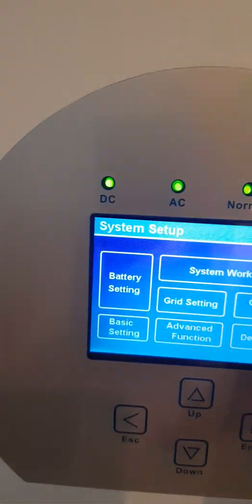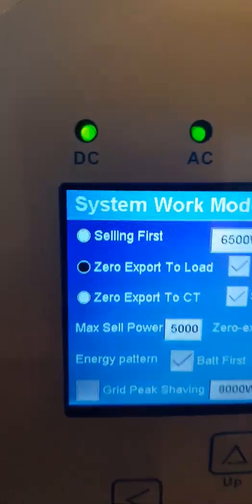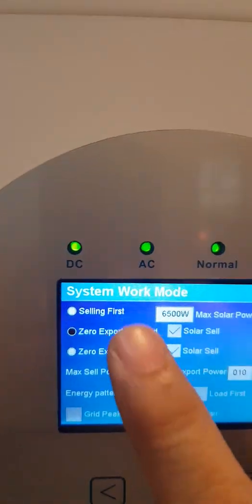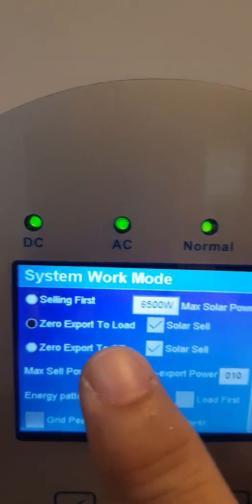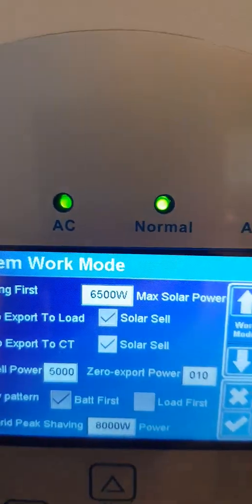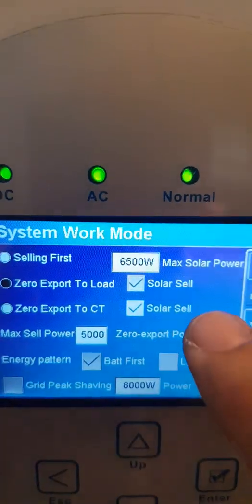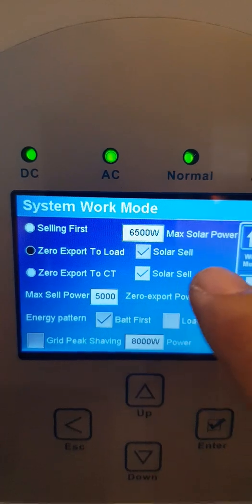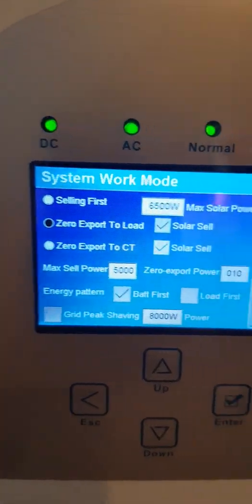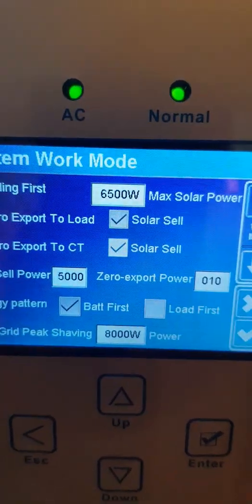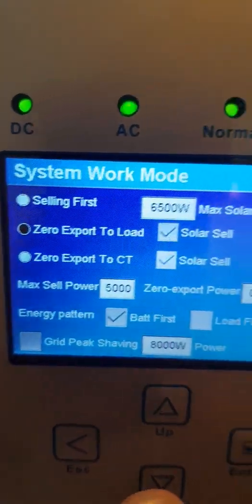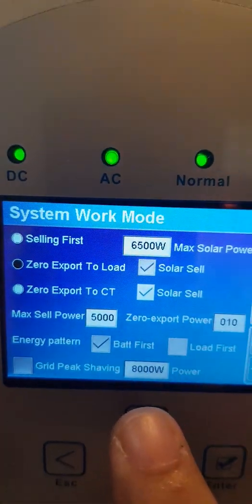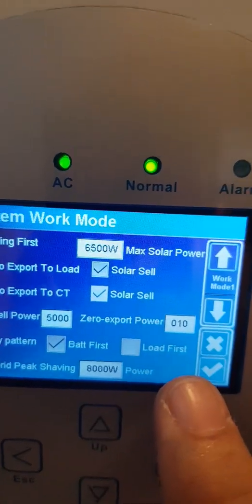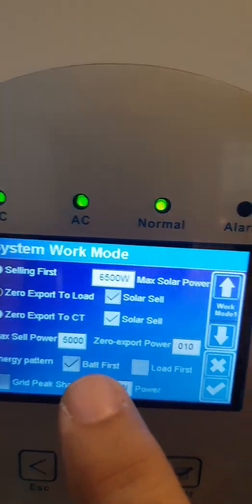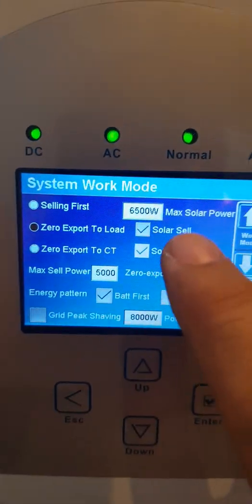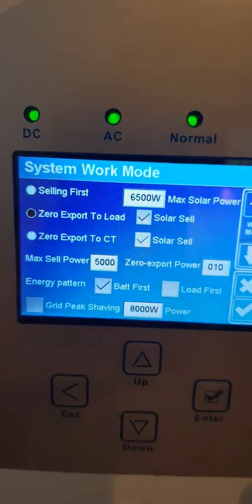Escape. So system work mode. If you're selling to grid, you can do selling first. Or right now we are using zero export to load. So solar sell is checked, so I can sell energy back to grid. You can turn this off so that the limiter will work and you will not export energy to the grid. So what else? So energy pattern, it means battery first, that you will charge the battery first and excess energy will go to the load. If you have net metering and under solar sell, it will sell back energy to grid. If this is unchecked, you will not export energy.